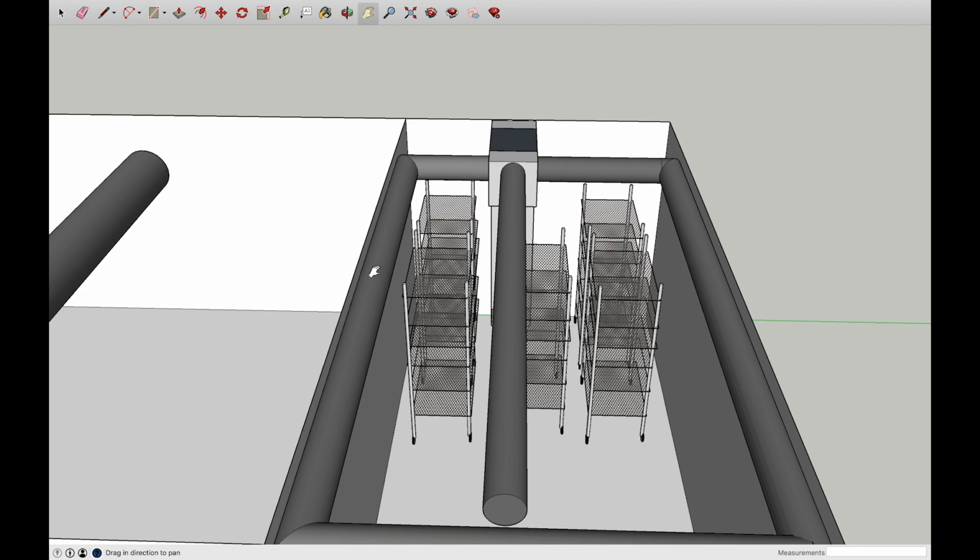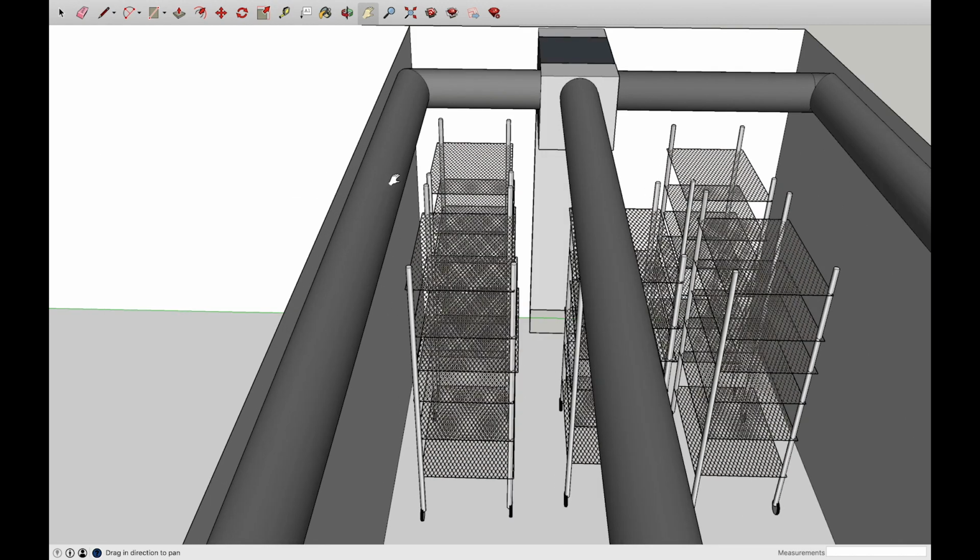So we have laser cut holes at the 6 o'clock position, so directly pointing down around the entire perimeter. With this air gap, it's basically an air channel that's going to allow the air to drop all the way down, and along its way, it's going to start making its way into each rack all the way down. The center duct here is a little bit different.